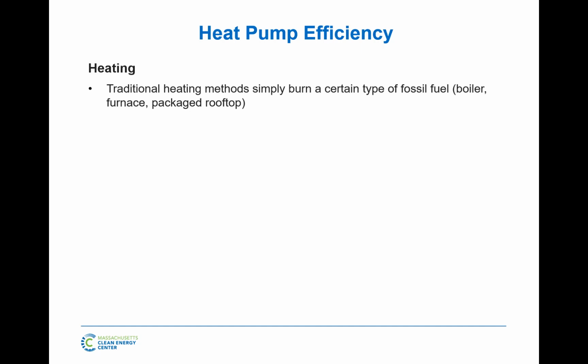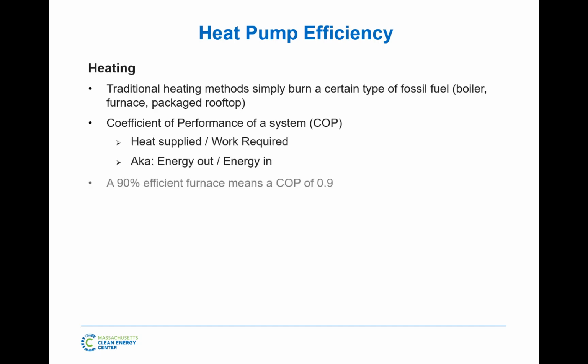Most heating methods use some sort of fossil fuel, whether it's a furnace, a VAV rooftop unit, a packaged rooftop unit, or a boiler. They all use some sort of fossil fuel. So a way to figure out how efficient the systems are, instead of EER in heating, it's common to use COP. It's actually the same thing, it just uses different units. It's heat supplied over work required.